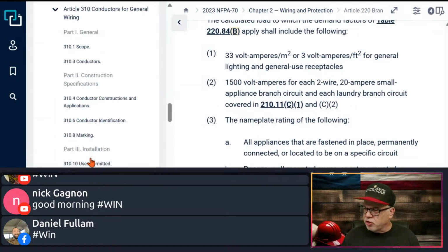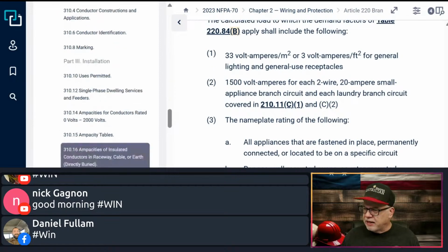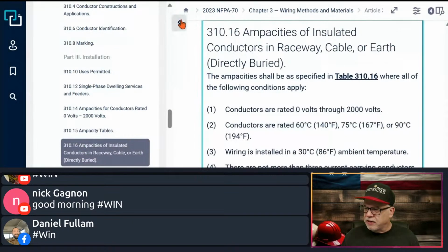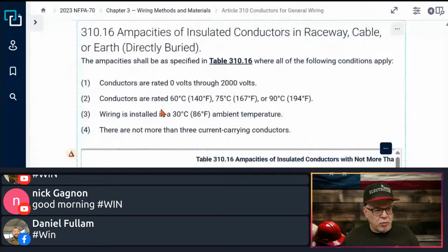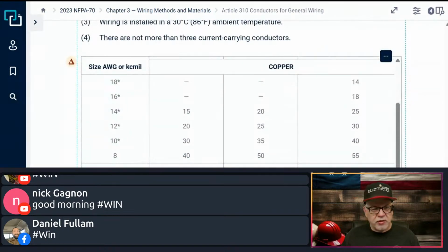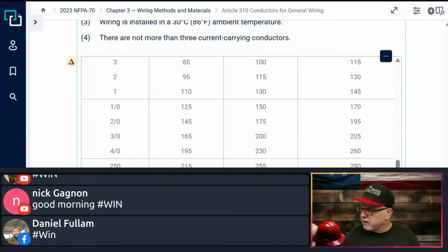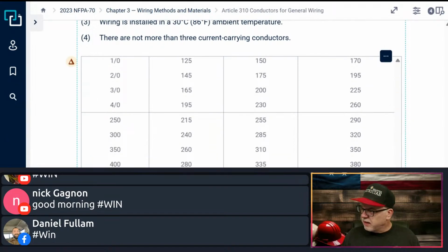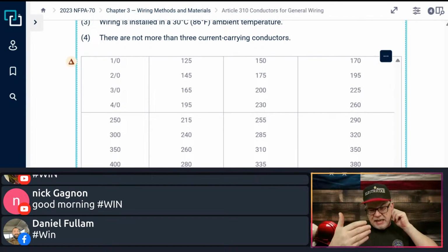That's the logical approach to how you handle conductors and the bending, and it just makes it a nightmare when you start getting over 500 kcmils. Even then, it pushes it. So here's the ampacities right here. If I would do a single conductor, it'd be 416 amps. We go down here, and it would have to be a 600. Okay, keeping to my golden rule, I like to keep it below that.